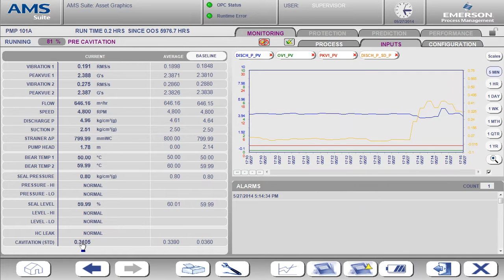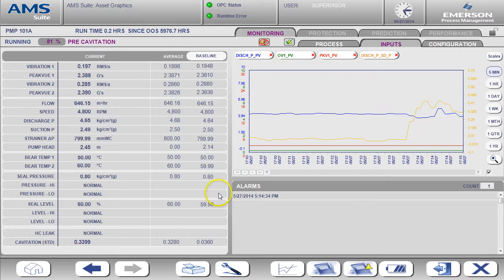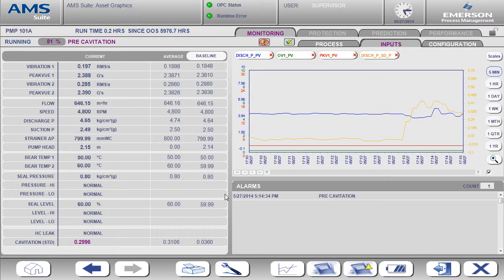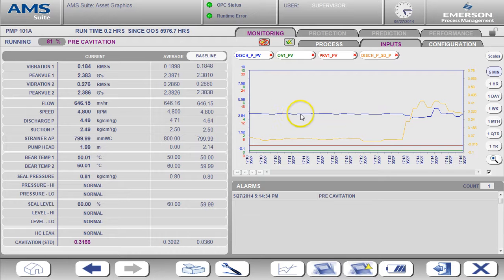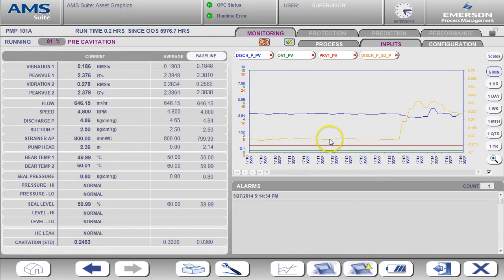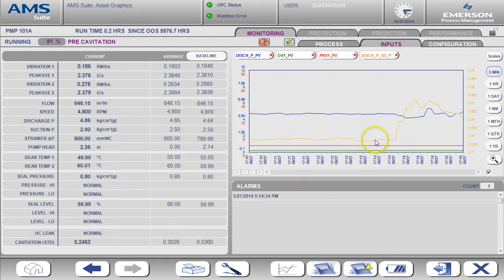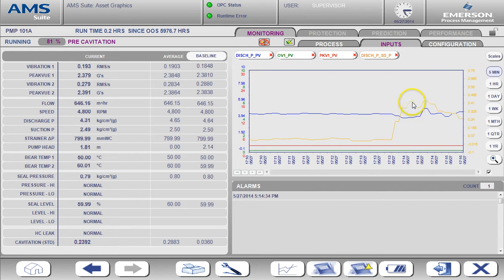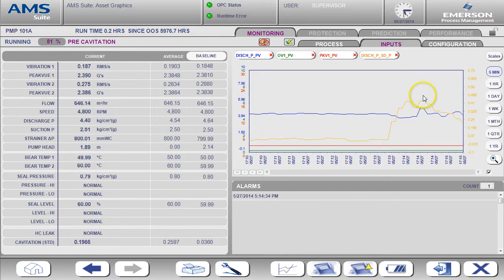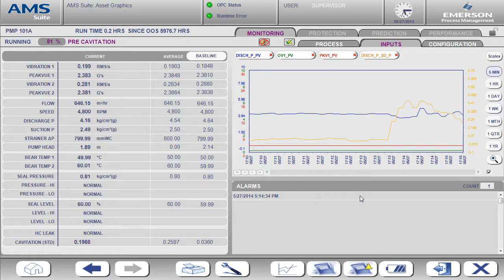This time I'm going to add the standard deviation of the discharge pressure. The reason I'm looking at this value is because we expect the discharge pressure to change with flowing conditions. However, we don't expect the variation in this value to change. Because the standard deviation of discharge pressure has gone high relative to the baseline, the pre-cavitation alert is active. At this point, none of the vibration inputs are high.